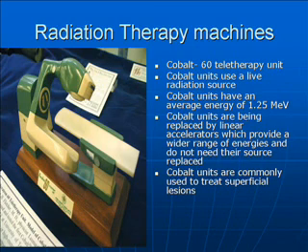Radiation therapy machines: the cobalt-60 teletherapy unit. Cobalt units use a live radiation source and have an average energy of 1.25 mega-electron volts. Cobalt units are being replaced by linear accelerators, which provide a wider range of energies and do not need their source replaced. Cobalt units are commonly used to treat superficial lesions. The unit shown on this slide is from the early 1950s.